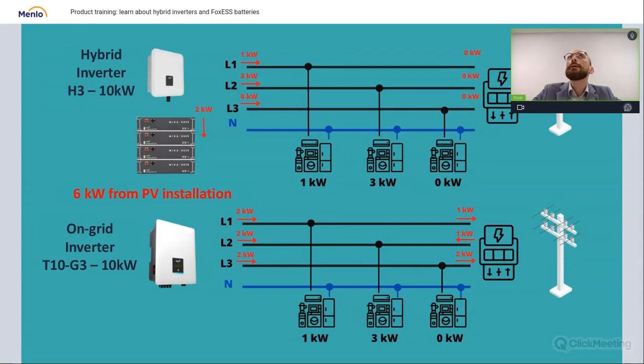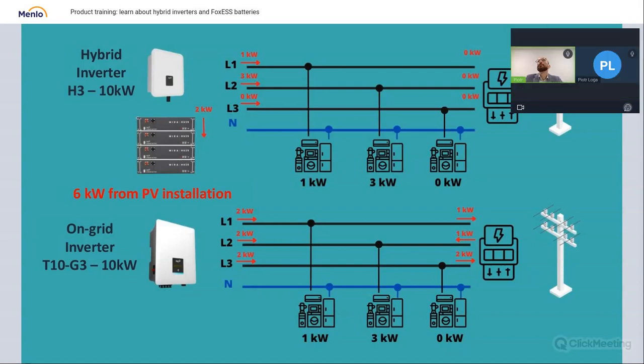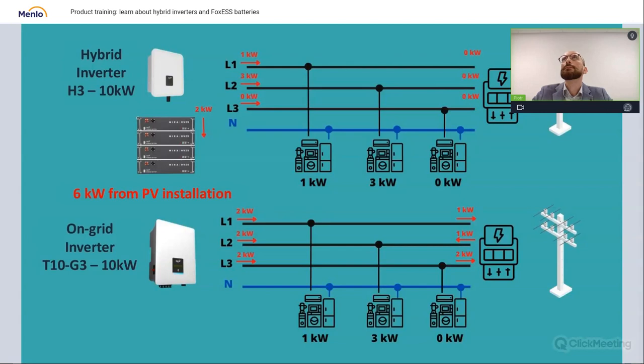And I believe we may output this energy. If we have 10 kilowatts, we can output 3.6 kilowatts on every phase, or output no energy on some phases. So you have from 0 to 3600 watts per phase. Okay. Thanks. Okay.